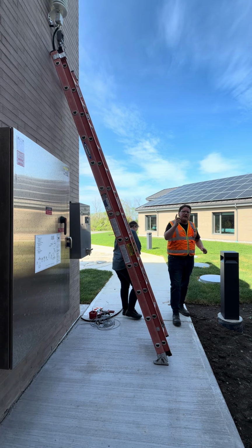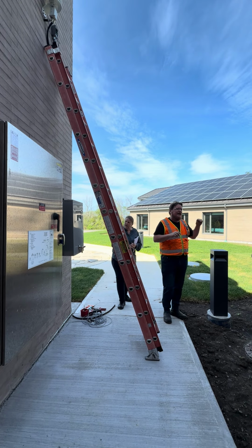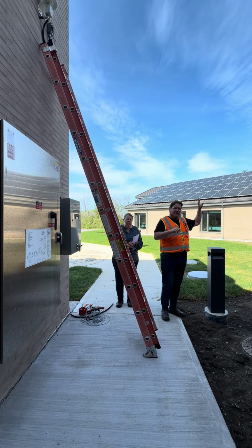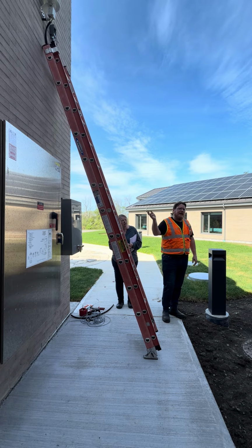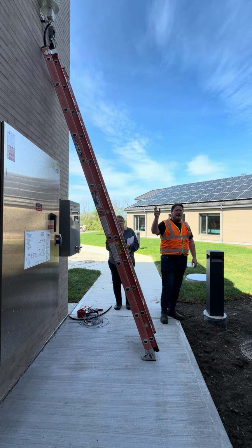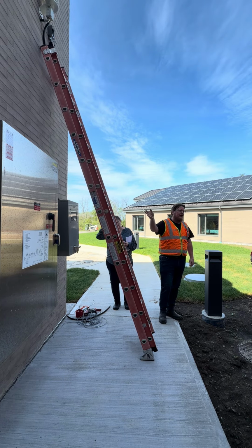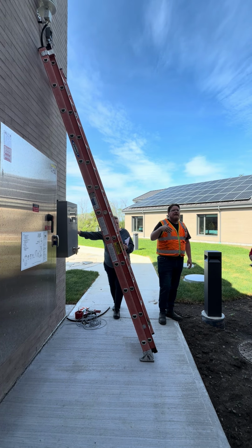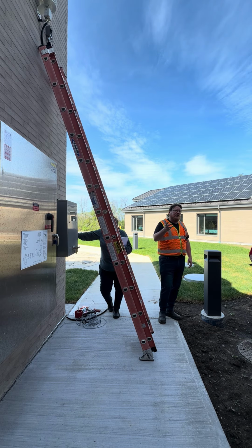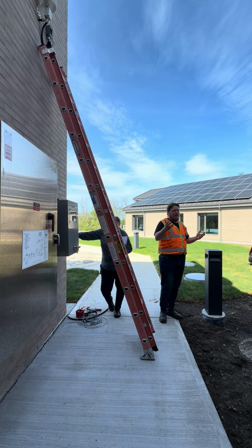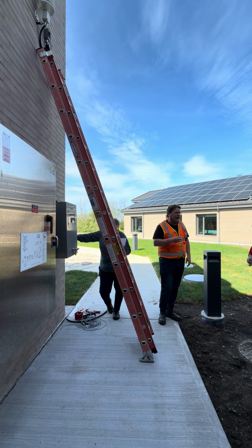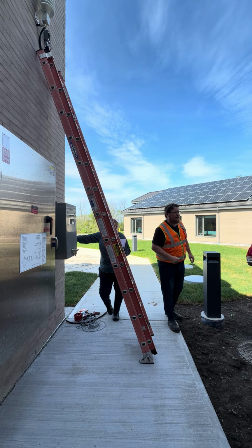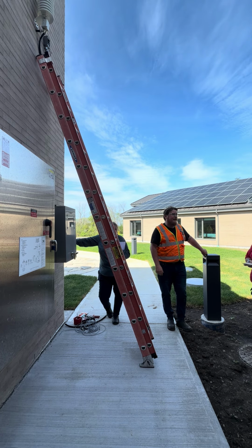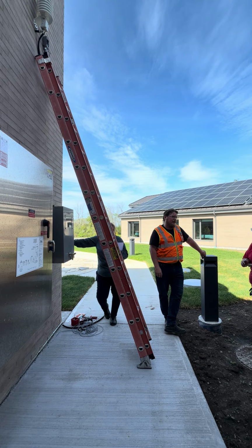There's a tower that communicates with the Hydro One substation. If they have a problem on the load side, they can choose to disconnect the system automatically. So when that happens, you would get an alert from the inverter system saying, hey, we're offline. That's a point to reach out to Hydro One and say, okay, is there some problem? What's the issue? How do we get reconnected? So they can disconnect off-site? They can disconnect off-site. Okay. So it's a remote transfer trip.